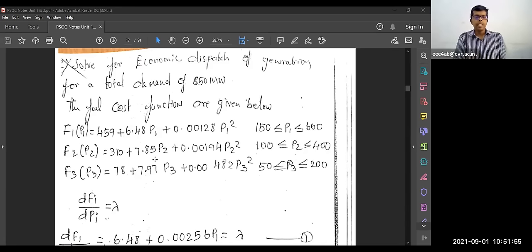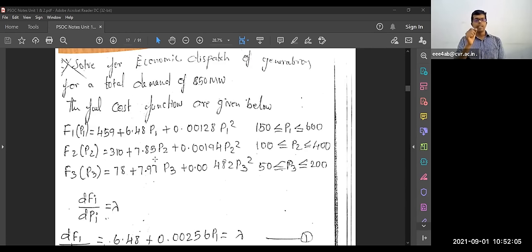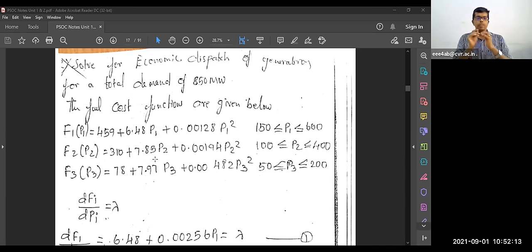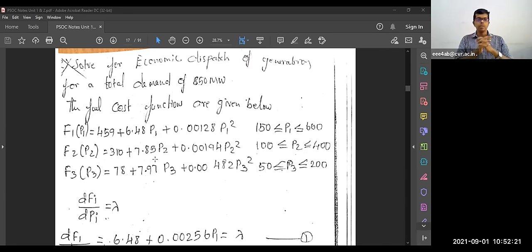What is the general formulation we derived? The general formulation is DFi/DPi = λ. That is the economic load dispatch condition for N thermal generating units. We have to substitute i = 1, 2, 3 because three generating units are given — that is DF1/DP1, DF2/DP2, and DF3/DP3.